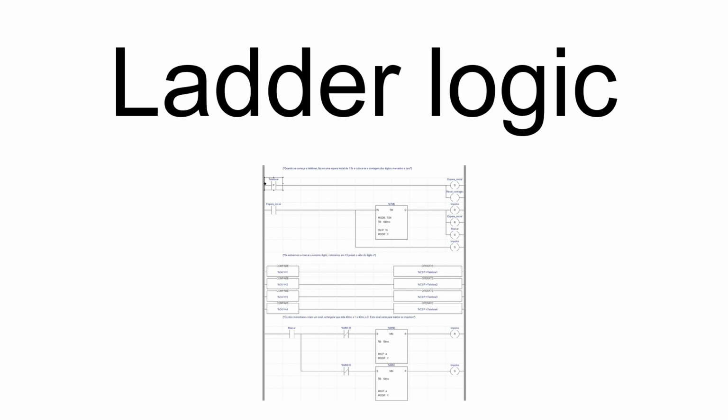While ladder diagrams were once the only available notation for recording programmable controller programs, today other forms are standardized in IEC 61131-3. For example, as an alternative to the graphical ladder logic form, there is also a more assembly-language-like format called instruction list within the IEC 61131-3 standard.